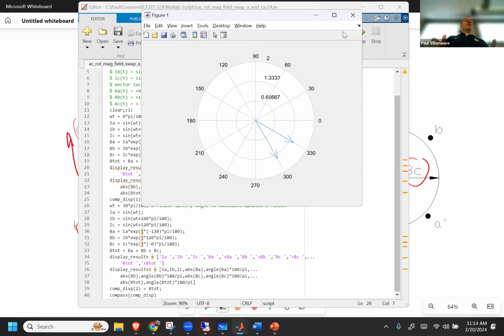Whenever you do a new application, where you bring a motor in and want to couple it up to a pump, the very first thing you do is put the motor on the stand and decouple it from the pump. Make sure they're not coupled. Then you bump it, energize it for a second, and see which direction it rotates. If it rotates the way it's supposed to, you couple them together. If it rotates in the wrong direction, what do you do?